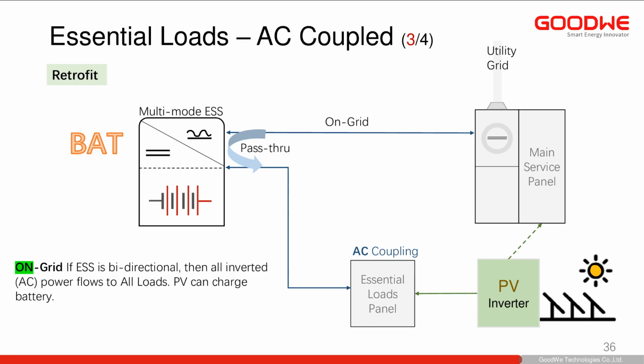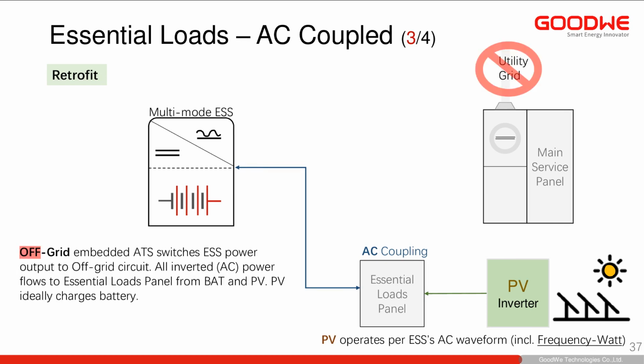And by the way, yes, this is a battery inverter. You don't need a PV inverter. We could do one, but a battery inverter, if you don't need additional PV, is all you need. So when the grid goes down, the ESS contributes power to the loads. The PV inverter contributes power. The PV inverter might make more power than is necessary. And so on a bidirectional ESS setup, that energy can flow back into the ESS and charge the battery.